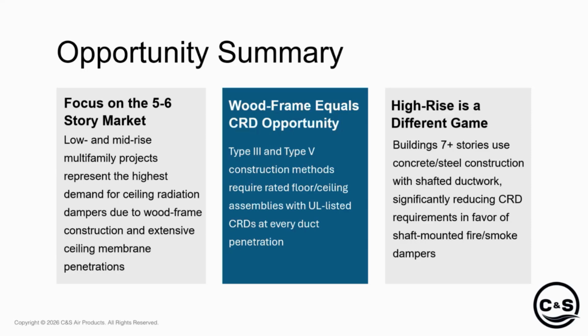Right. And Taylor, something that I get every now and then on the application side, maybe you can speak to this a little bit: how come we're starting to see requests for dynamic CRDs versus static? Can you give us a little color on that? Sure. So dynamic versus static, I should probably start there. Dynamic systems have the units running, your air systems running in the case of a fire. A static system is where you would have the unit shut off, so there's no airflow through your system.